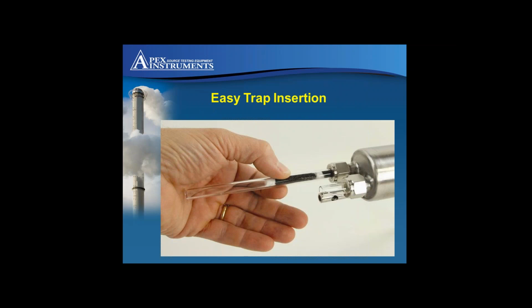We set it up differently here. Sample traps are easily inserted into the probe, as shown here. The weekly 7-day trap change should take about 20 minutes. However, we generally recommend that the profile runtime is set to longer than 7 days, perhaps 10 days, just in case you cannot get to the sample location to change the traps. For example, the elevator breaks down or personnel are absent.